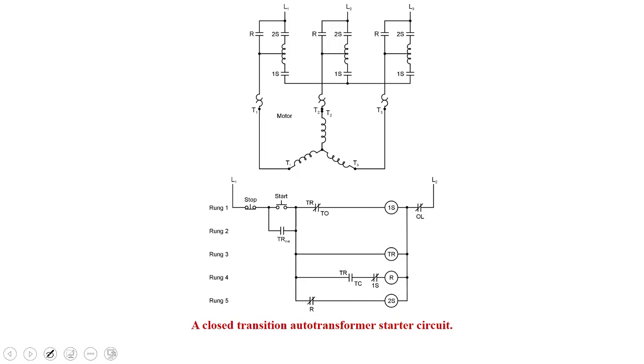Here's a closed transition auto transformer. So what this does, once again, is the motor will always have some sort of supply voltage on it as we go from start to run. Let's go ahead and follow this through. Starting on rung 1 here, we press the start button. The start button goes through this normally closed contact of the timing relay and energizes coil 1S. What else does it energize? The timing relay. We've got a set of instantaneous contacts then, acting as a holding contact from our timing relay.